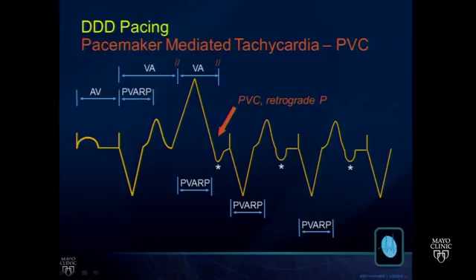The solution to pacemaker-mediated tachycardia is to have a longer PVARP that's either triggered by a PVC, programmed as baseline, or some other modality of PVARP prolongation that occurs in response to a PVC. So the bottom line is that we want to have a longer PVARP either after a PVC or in general so that PMT cannot be triggered. Now you see that you have a PVC which interrupts the VA interval. There is retrograde atrial activation, but this time that P wave falls within the PVARP, so the device cannot respond to that retrograde A by providing triggered ventricular pacing, and nothing happens.